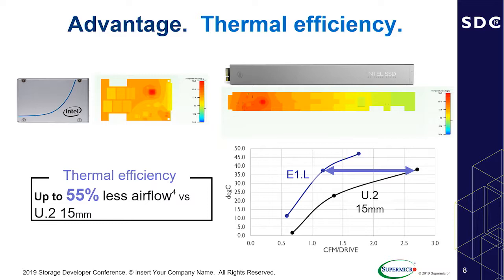And because of that, what that means, I can slow down my fan. What does that mean? I don't have to use as much power because those fans take power. And they especially take power as they run faster. It's not linear. They take a lot more power as they run faster. So if I can slow that fan down, now I can save you power. Now the total cost of ownership seriously reduces because I don't have to use that much power on my thermals.